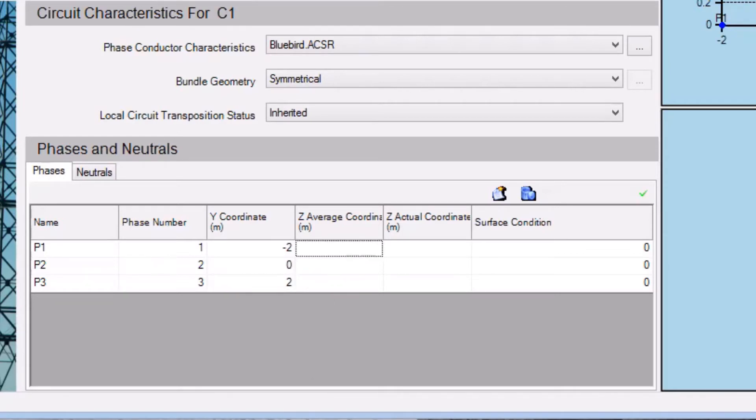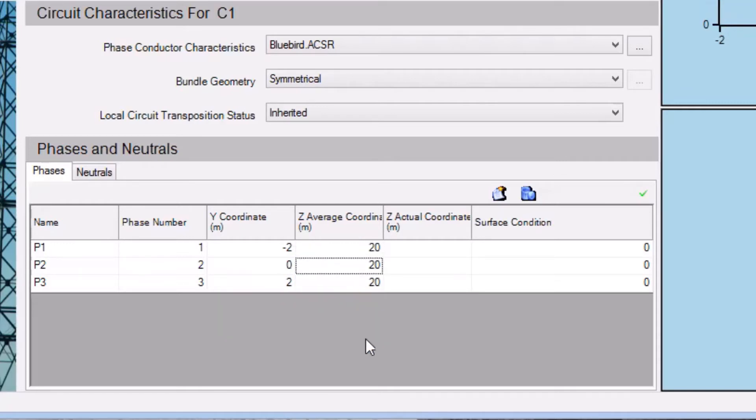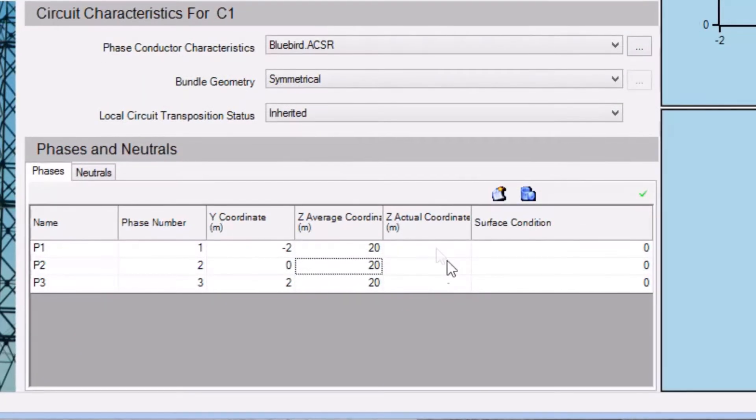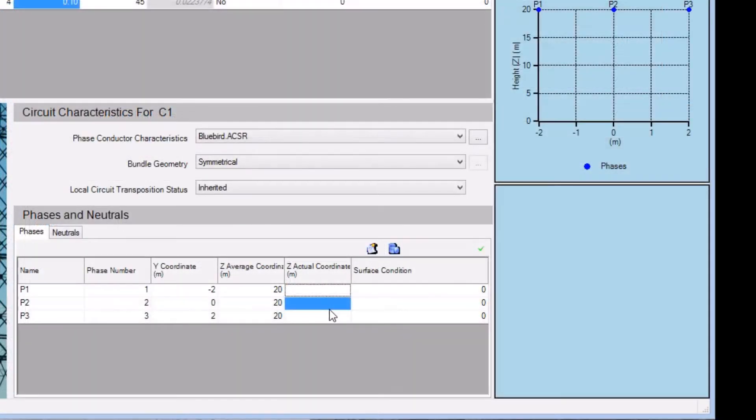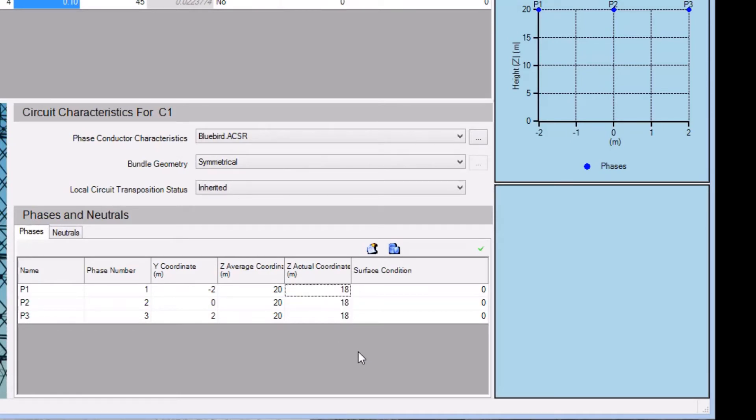For the z-average coordinates, we'll enter a value of 20 meters for each phase. The z-average coordinates correspond to the average height of the bundle center between towers, taking into account line sag. The z-actual coordinates correspond to the height of the bundle directly above the observation point. Here we'll enter a value of 18 meters for each bundle.